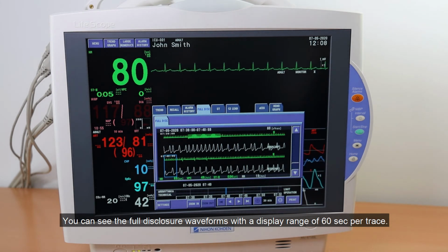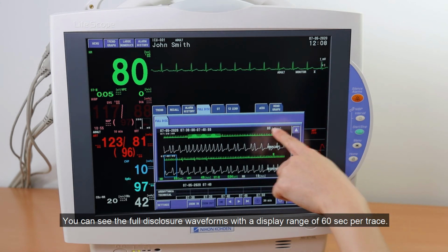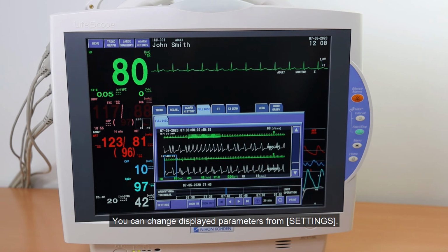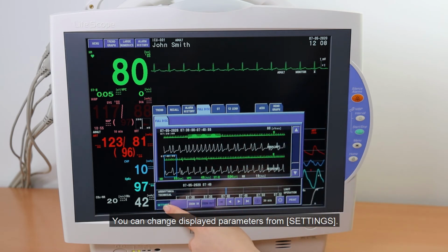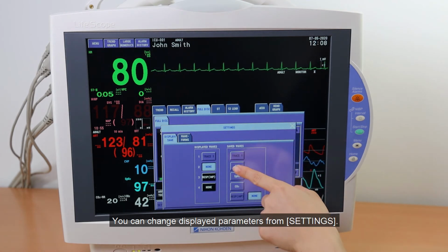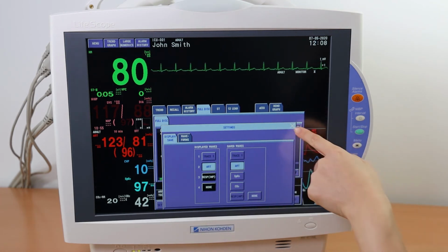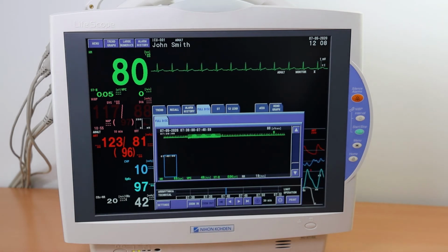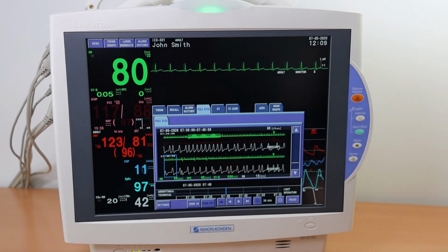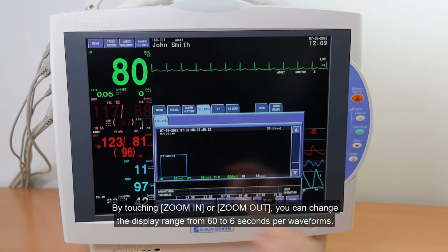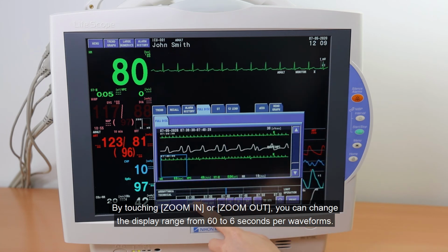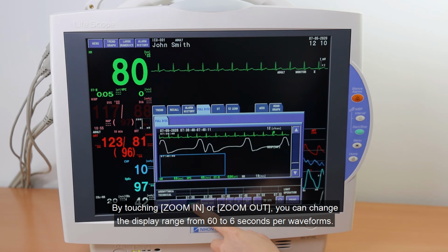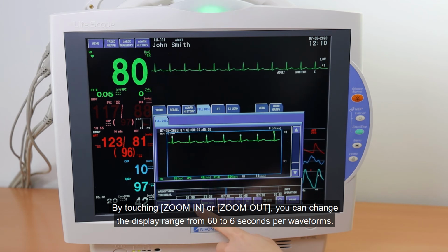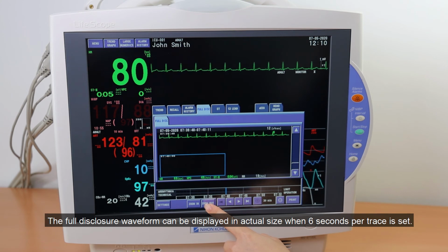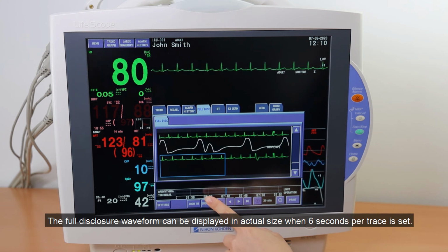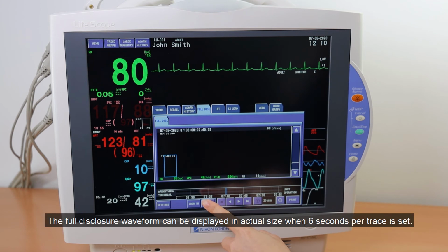You can see the full disclosure waveforms with a display range of 60 seconds per trace. You can change displayed parameters from the Settings key. By touching Zoom In or Zoom Out, you can change the display range from 60 to 6 seconds per waveform. The full disclosure waveform can be displayed in actual size when 6 seconds per trace is set.